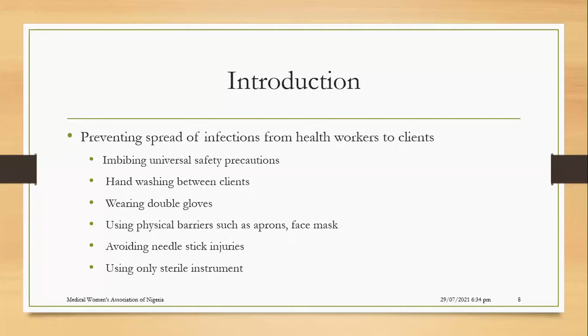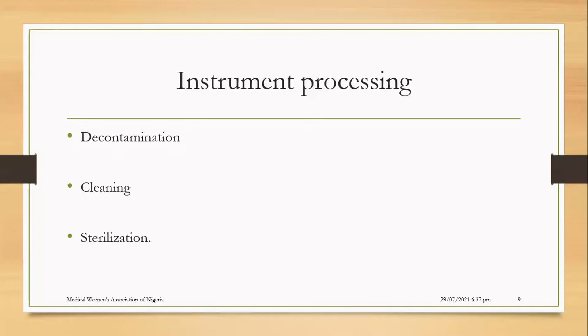Then after decontamination, they should be cleaned, and after cleaning, they should be sterilized. This is very important. But as I'm telling you from the experiences I've had, ensuring that these processes are done can be a very, very big challenge, especially the sterilization and the decontamination. So what do we mean by decontamination? Decontamination is the first step for instrument processing.